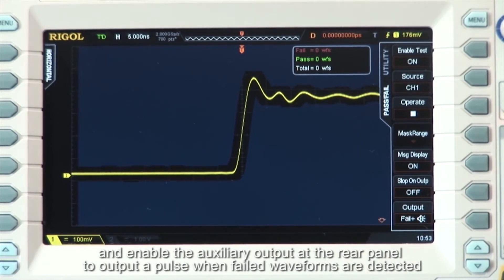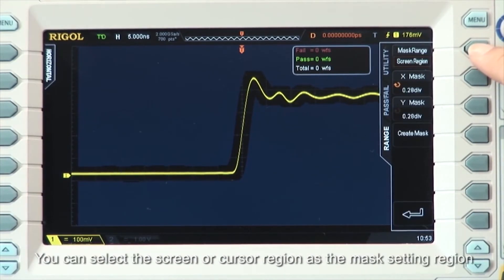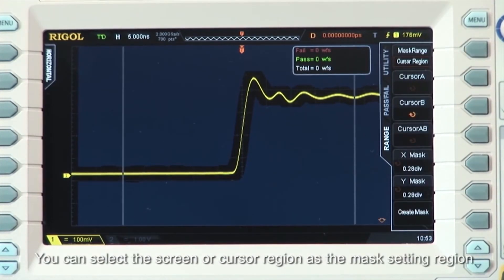Before enabling the test, set the fail region according to your test requirements. You can select the screen or cursor region as the mask setting region.